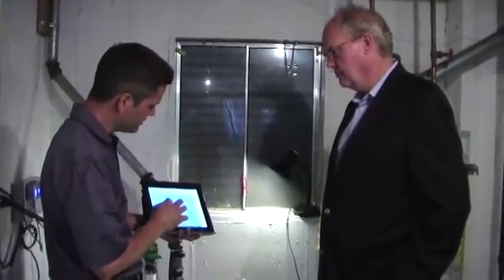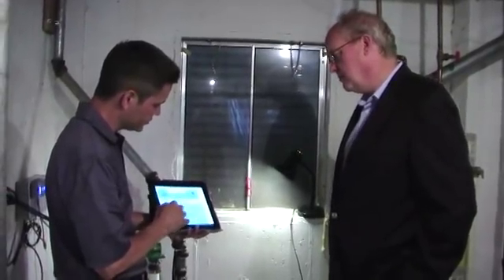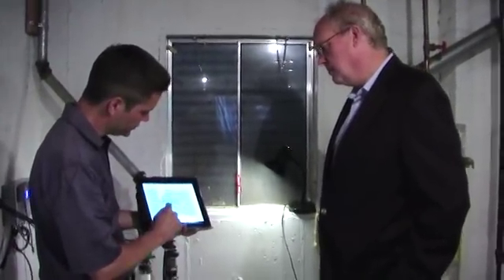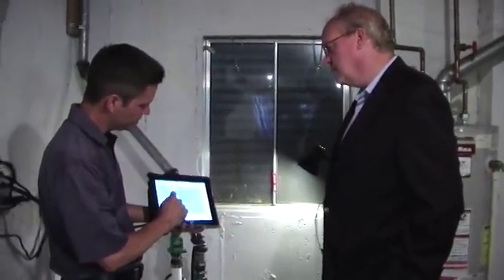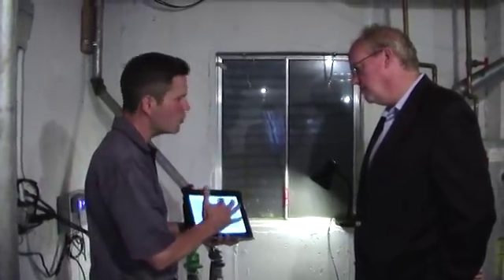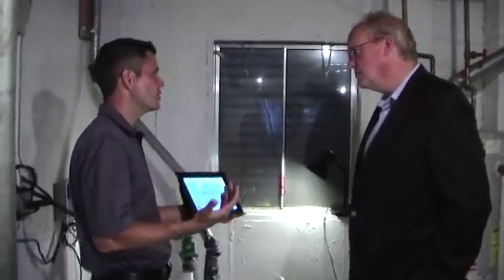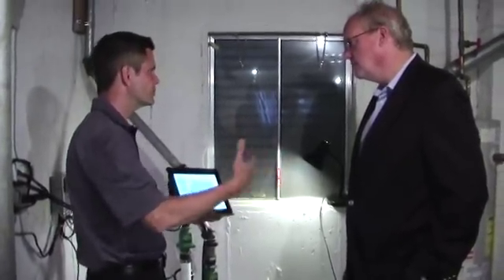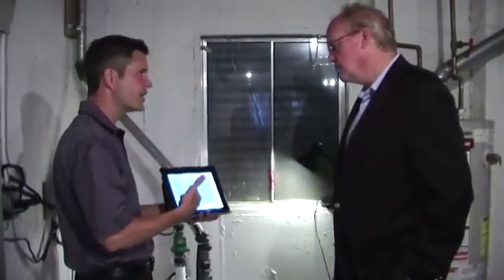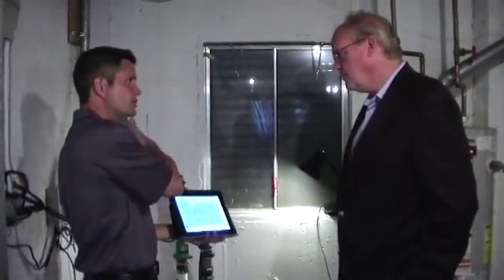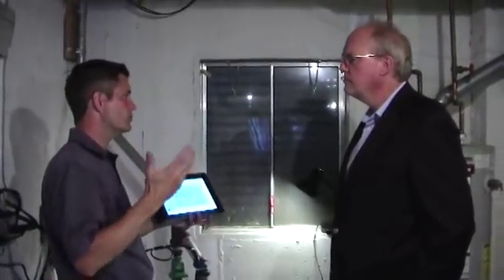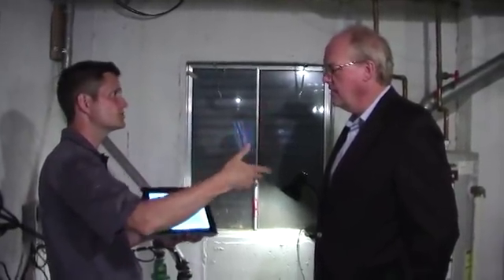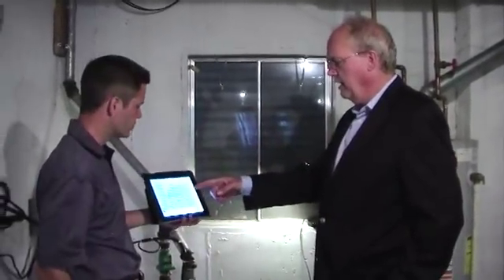Back on the Config screen, there's another field called AOK Notify, set at 120 minutes — that's just our testing default. You're probably going to want it set for maybe seven days or even every day. If you're not getting an alarm, you might still wonder if everything's okay. The AOK tells the controller: as long as there are no alarms, go ahead and send an AOK email. It's just positive reinforcement that everything works.